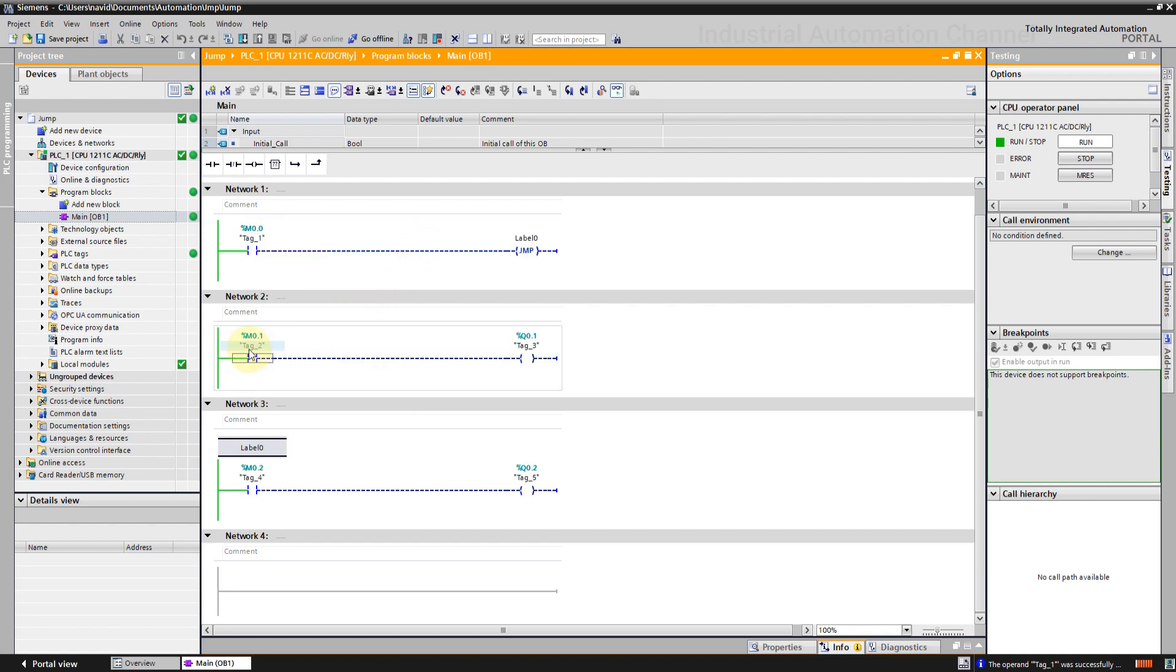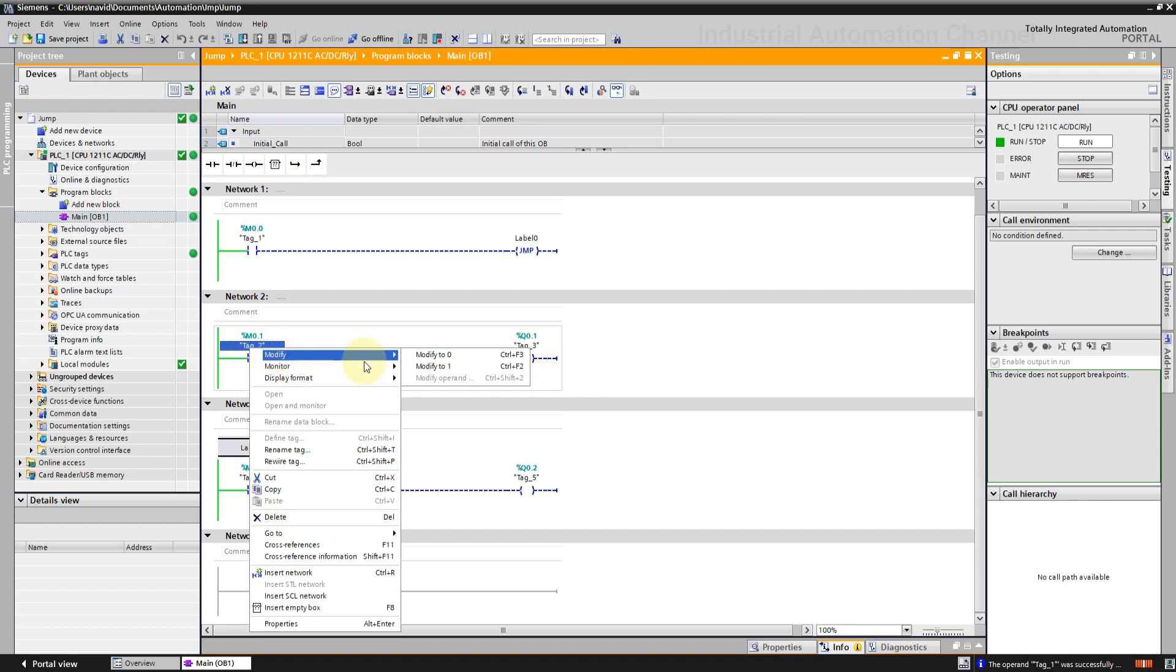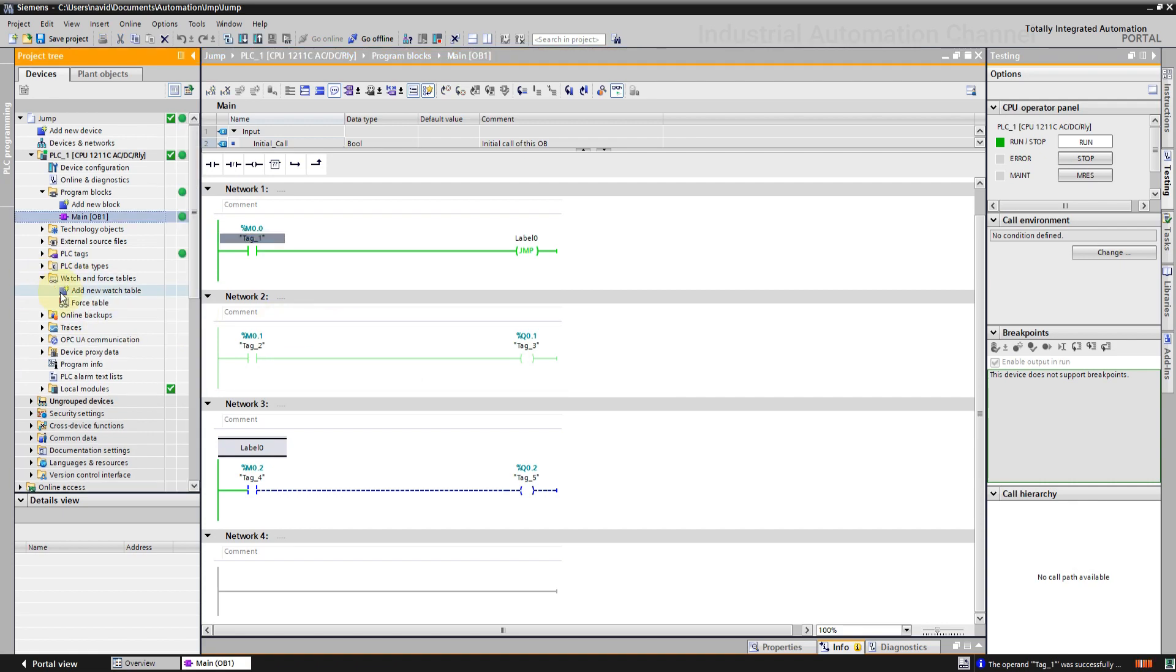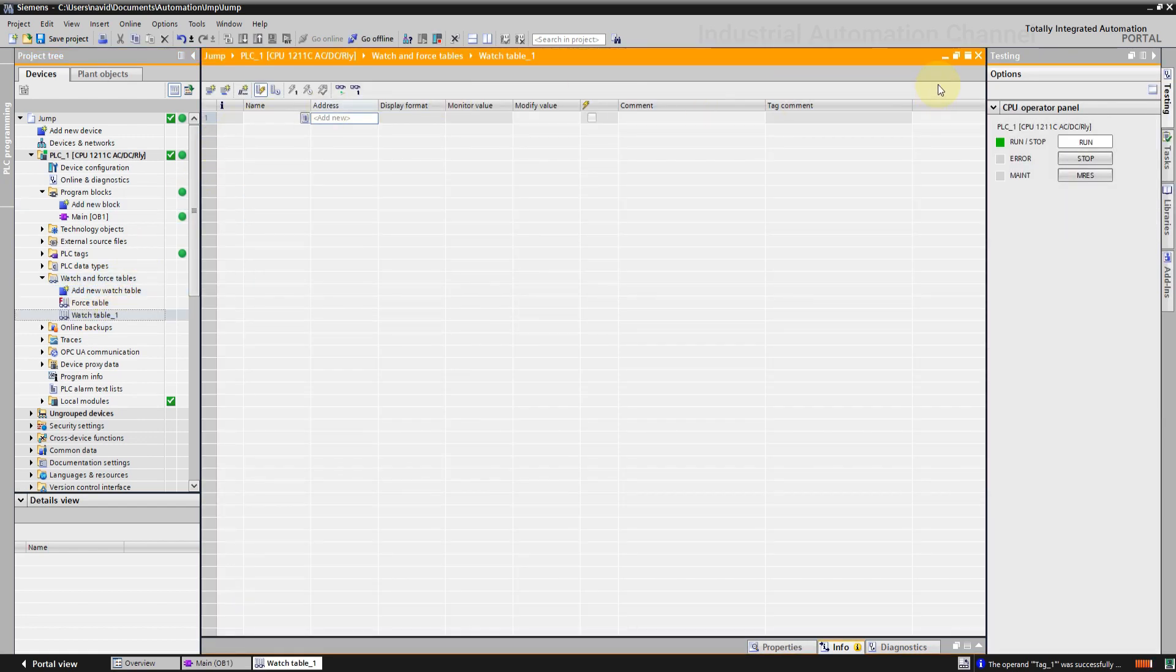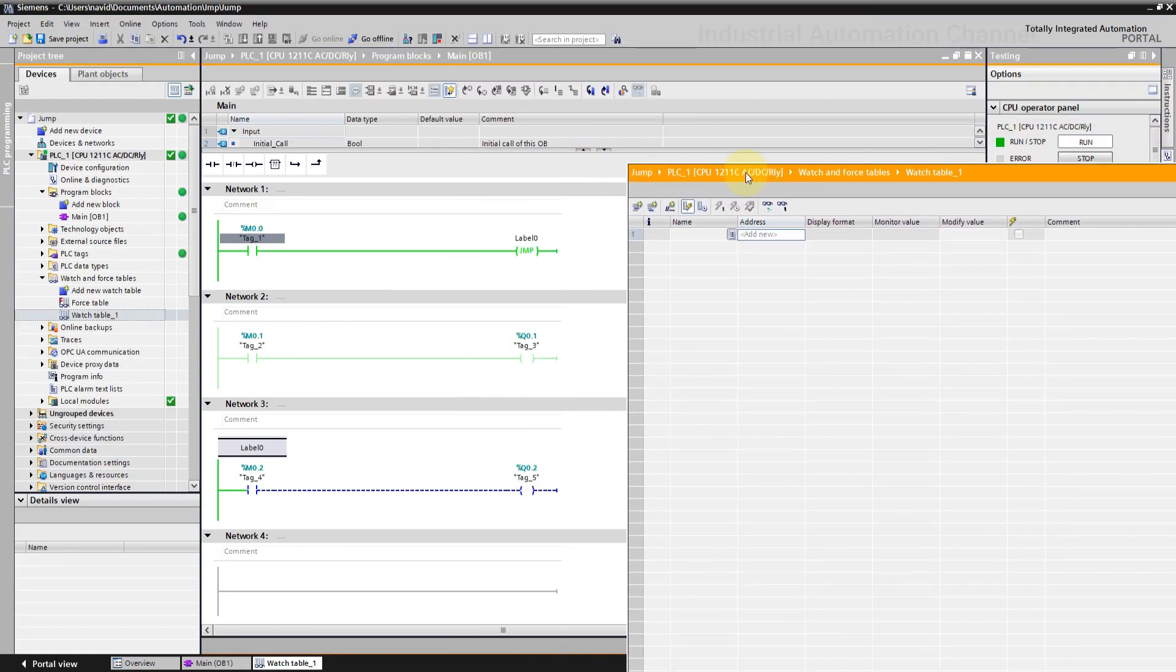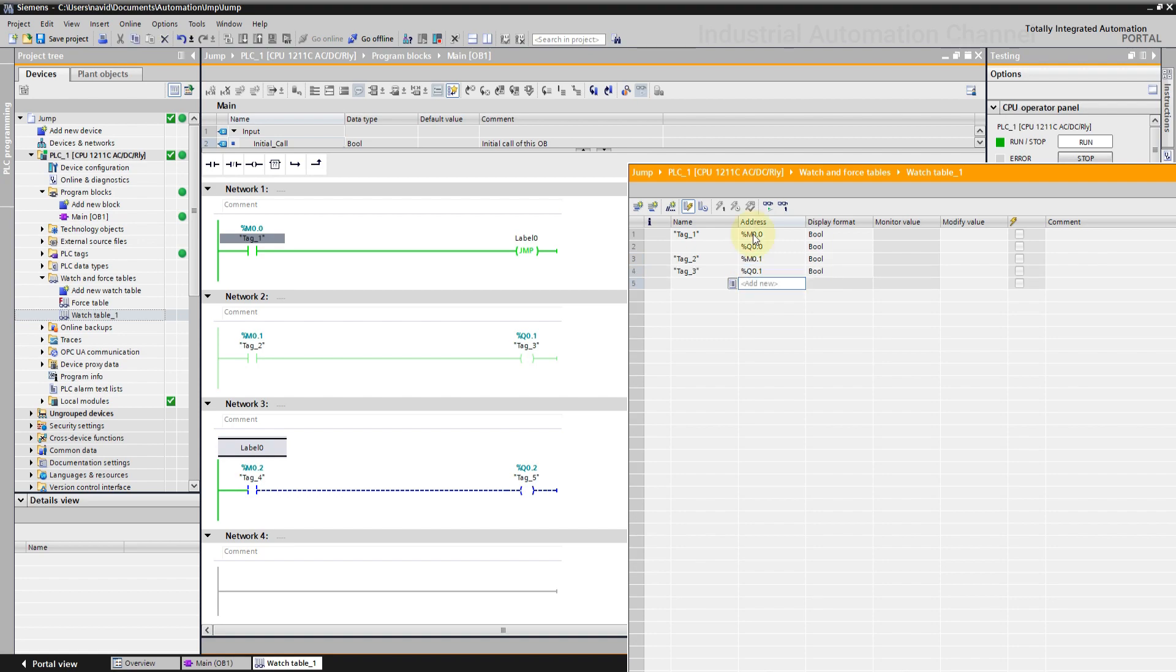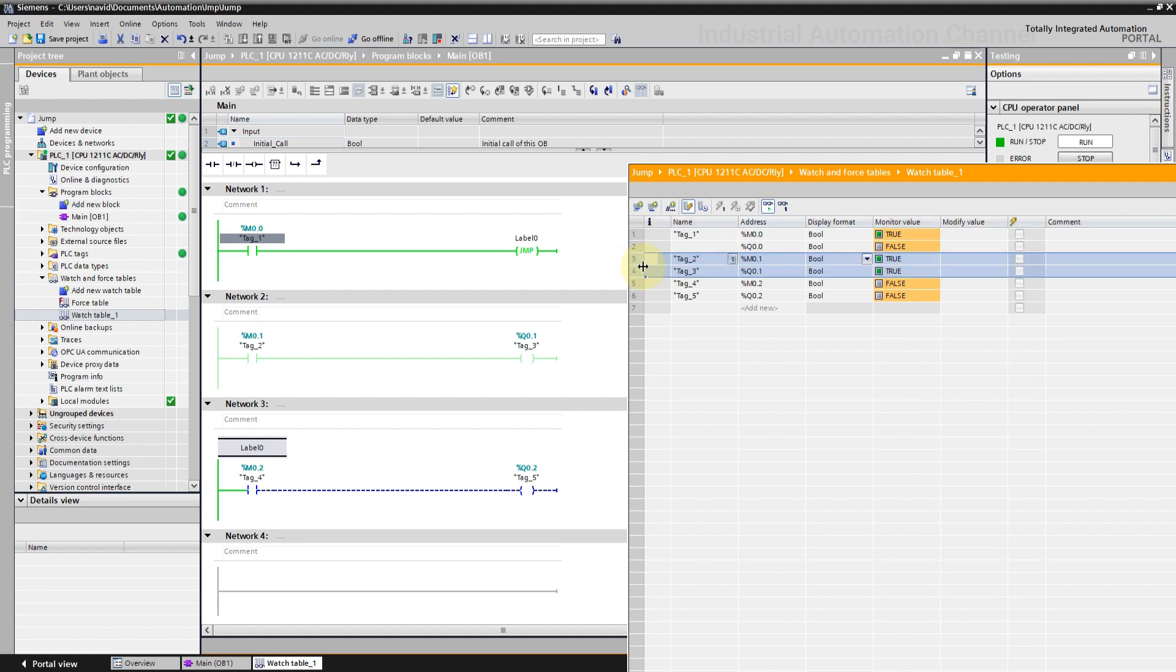Now suppose this contact is already on before I activate the jump. m0.1 and q0.1 are on. Let's activate the jump and see what happens. You see this network is again light green. But are the input and output now off? Let's see in a watch table. As you see m0.1 and q0.1 are both on.